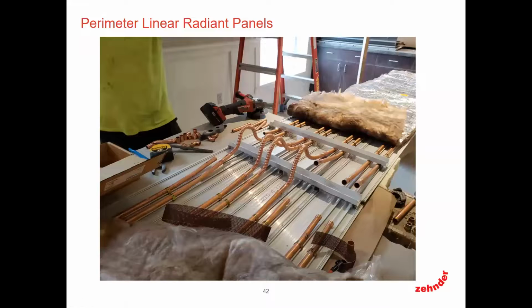I mentioned a little bit earlier about the U-bends and interconnects shipping loose. Again, I like to show these things because I like our designers to understand what they're actually getting in the field. So in this case, when you start having a 2-tube, 6-inch extrusion, you can really start adding the number of connections up very, very fast for the mechanical contractor to install and make those connections. Now, whether they're pro pressing them or they're soldering them, there's still a significant amount of work that needs to be done in the field if those items are shipped loose.